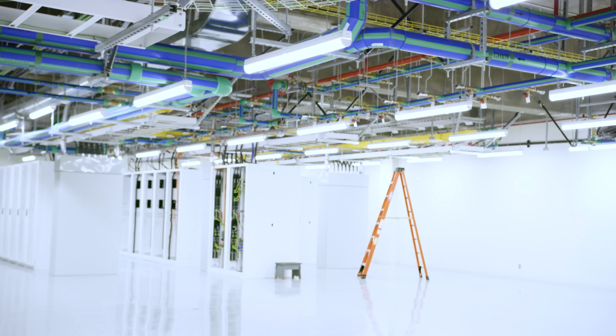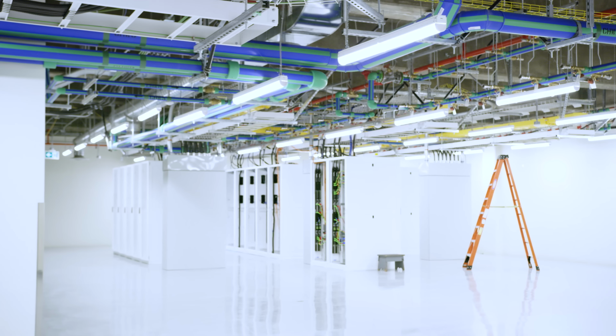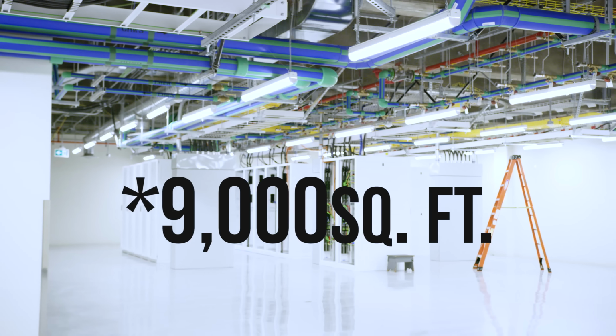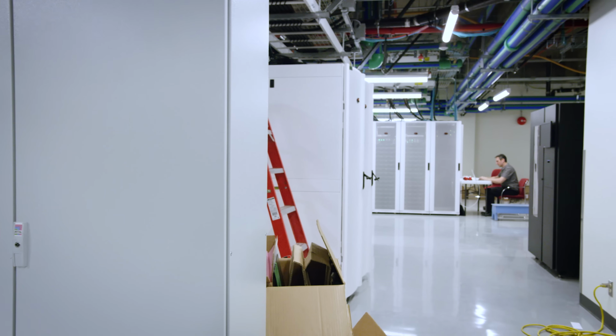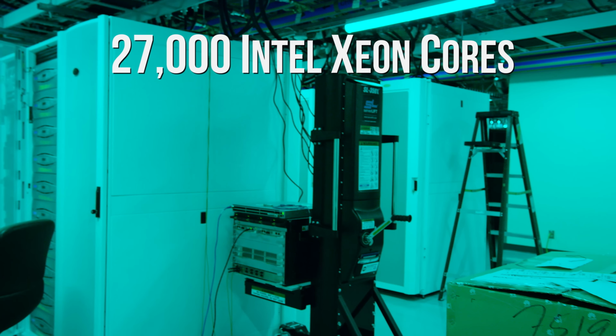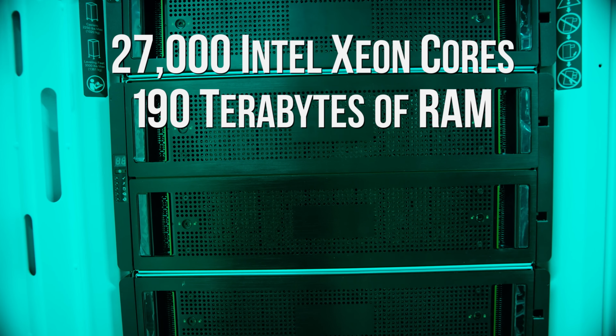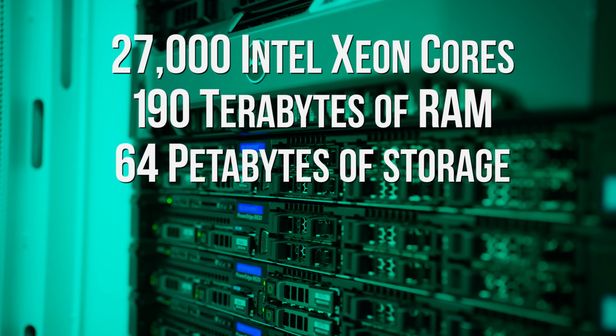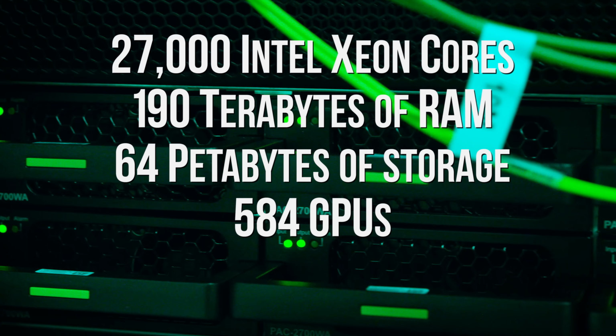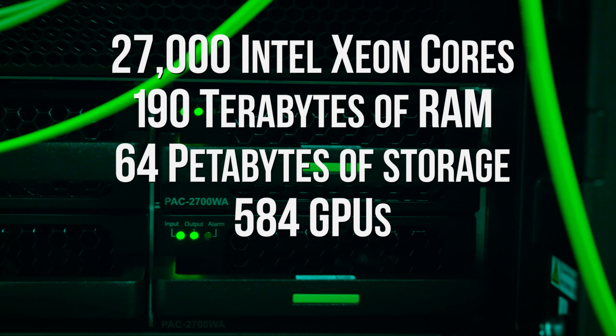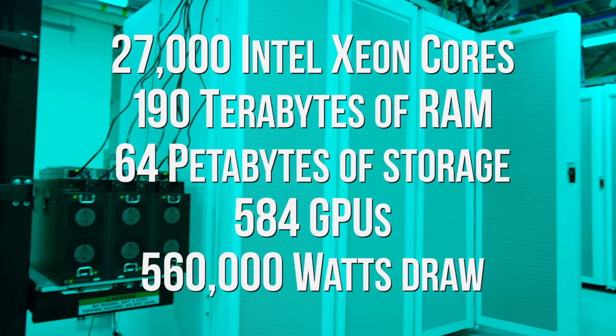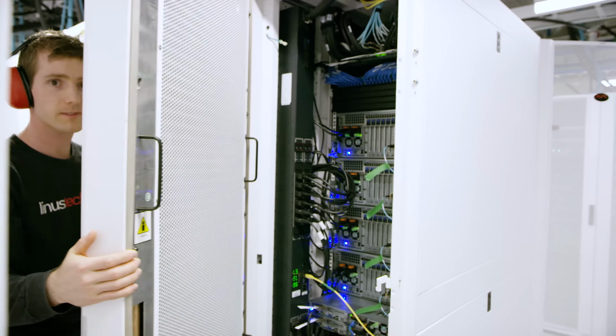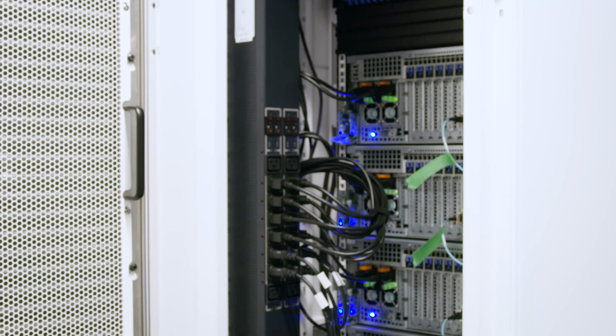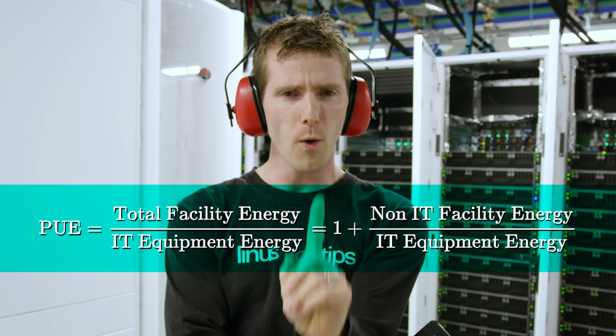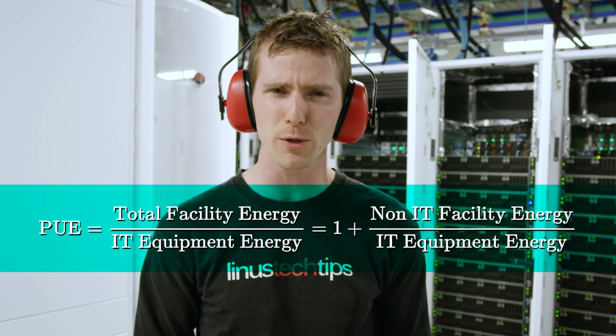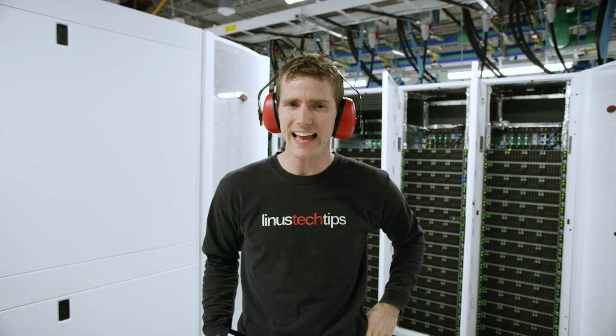So Cedar is a big data machine. It takes up a quarter of the 5,000 square foot data center it occupies, meaning actually that there's room for it to grow. But right now it has 27,000 Intel Xeon processing cores, 190 terabytes of RAM, 64 petabytes of storage, 584 GPUs, and a total power draw of 560,000 watts. Though, with that said, its efficiency is a shocking 1.07 on the PUE scale, where one would be perfect and a typical data center would be 1.5 to 2. We'll get into how they did that a little bit later though.